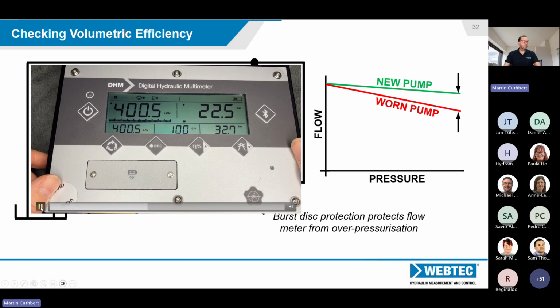Okay, so here what Steve's showing is you've got the flow that's actually going through the tester in litres per minute there. You've got the pressure it's operating at, and we've pressed this button here, and essentially that's set the 100% condition for volumetric efficiency. We now have the load valve in there, so we can restrict the flow through the tester, and as we restrict it, the pressure goes up, and we're then looking for how much, as we can see on this graph, the flow drops off. So if we were just to fast forward a bit, let's go to about here.